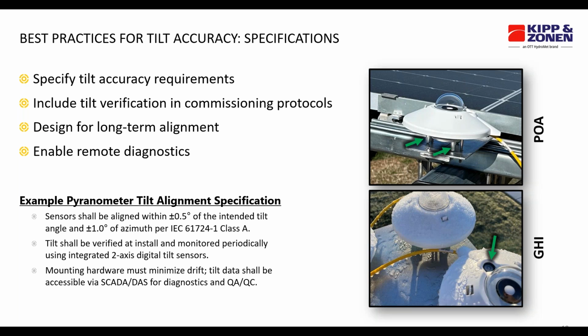And if you have operational guidance in the design spec, you might also consider including periodic tilt checks in the operations and maintenance plans, or using tilt data to verify correct sensor alignment and adjusting it only when it becomes misaligned.